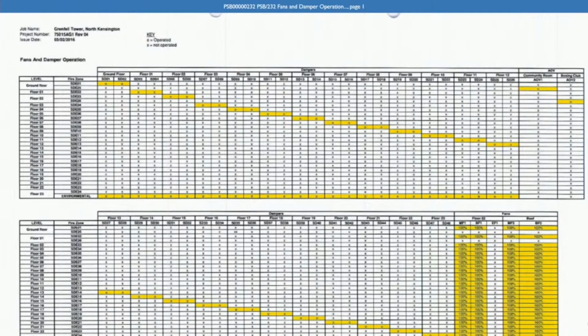So I think the fans are in the second table. They're on the lower side, yeah. On the right-hand side, we can see fans, floor 2 and the roof. And it tells us, we'll come to this in a moment, whether the fans are running at 100% or off. Is that correct? Yes. Well, 100%, and under pressure detection, they drop down to the lower speed.